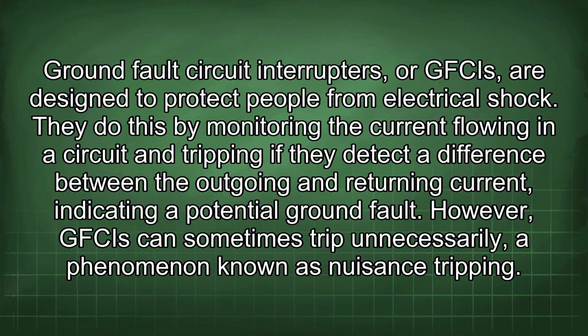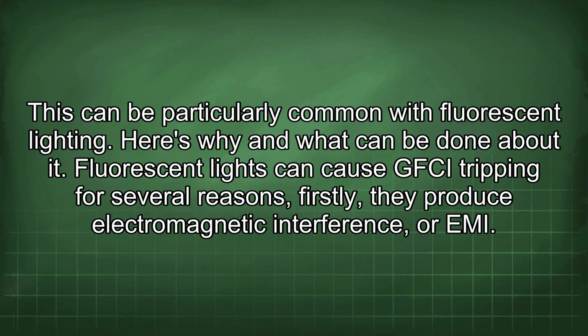Ground fault circuit interrupters, or GFCIs, are designed to protect people from electrical shock. They do this by monitoring the current flowing in a circuit and tripping if they detect a difference between the outgoing and returning current, indicating a potential ground fault. However, GFCIs can sometimes trip unnecessarily, a phenomenon known as nuisance tripping. This can be particularly common with fluorescent lighting. Here's why and what can be done about it.